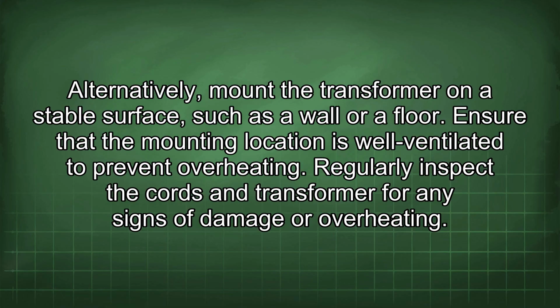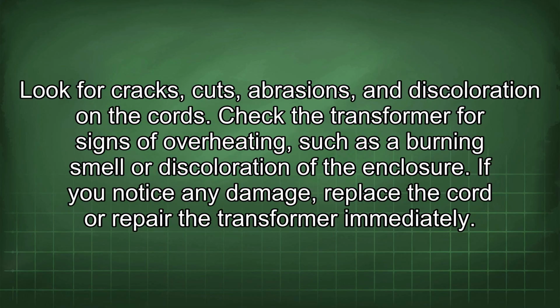Regularly inspect the cords and transformer for any signs of damage or overheating. Look for cracks, cuts, abrasions, and discoloration on the cords. Check the transformer for signs of overheating, such as a burning smell or discoloration of the enclosure. If you notice any damage, replace the cord or repair the transformer immediately.